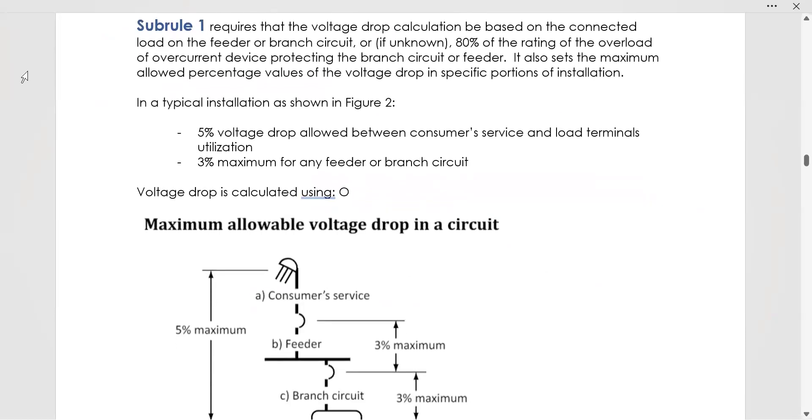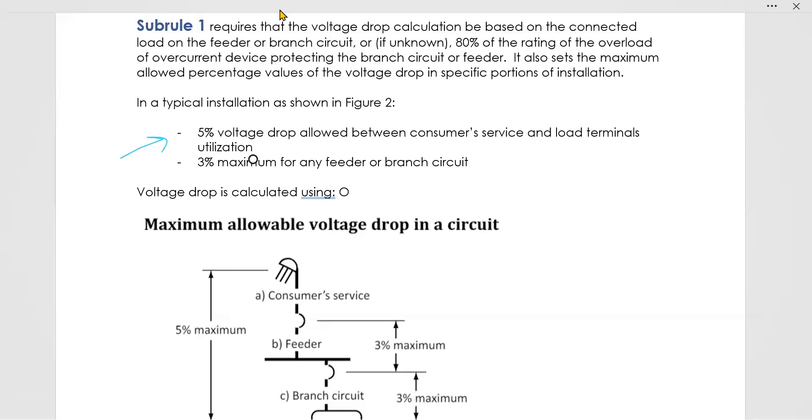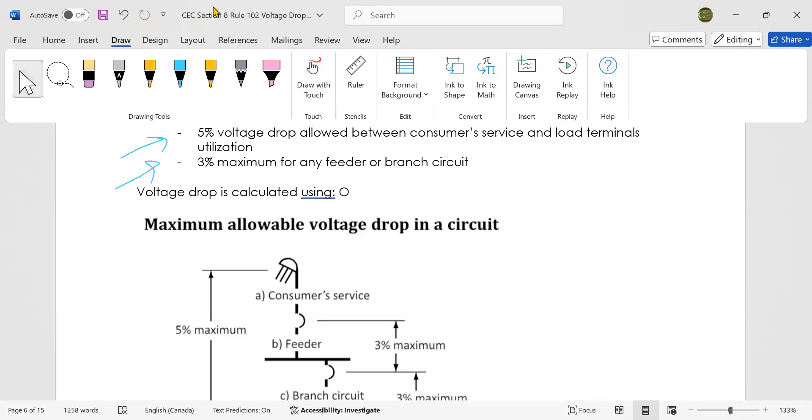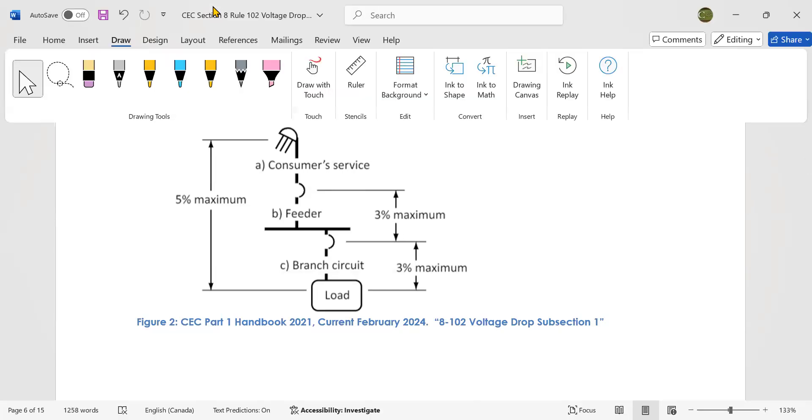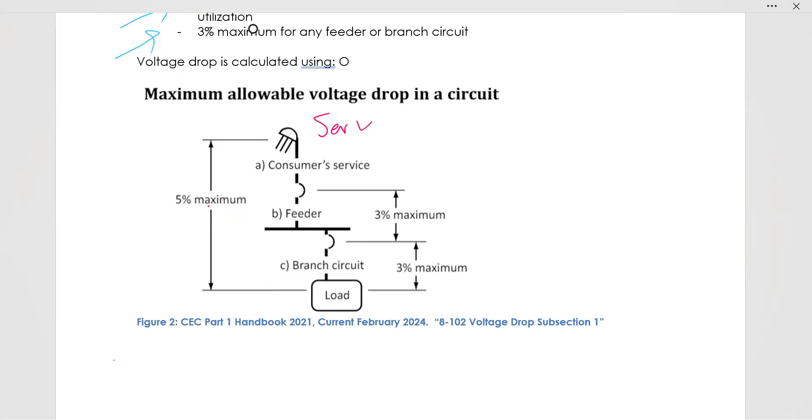So here we go. Subrule one, it basically looks like this. Can't be more than 5% between the service and the load terminals of utilization. So where it is supplied and where it is used, it can't be more than 5%, can't be more than 3% in any feeder or branch circuit in any one. So here is a nice diagram. This comes from the Canadian Electrical Code part one handbook. This one is the 2021 edition. This is also published by CSA. Thank you, CSA, for publishing this. I love this picture. It says, here's a service and here's the load. And between the service and the load, you can't have more than 5% of your voltage dropping. You cannot have more than 3% dropping between feeder and branch. You cannot have more than 3%, sorry, in the feeder. And you cannot have more than 3% in the branch. That's what it says. That is subrule one. Pretty simple and straightforward.